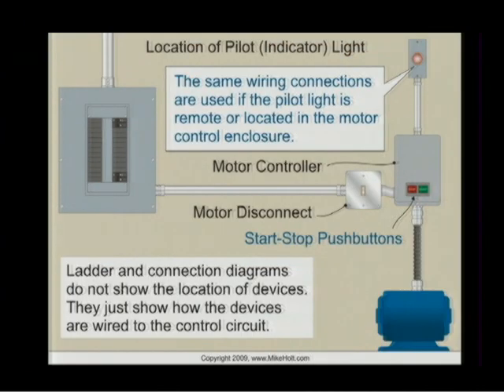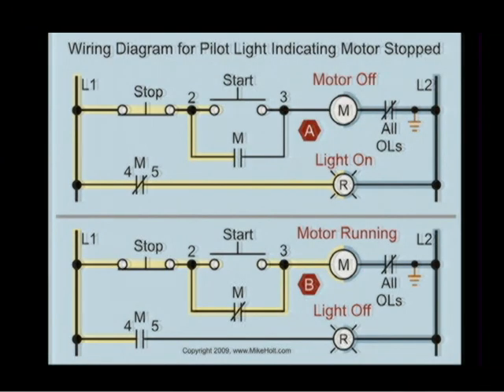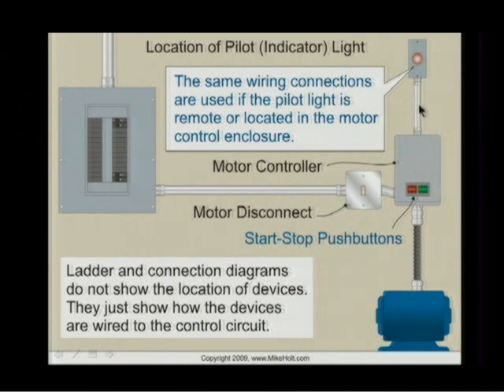All right. And where do you locate the pilot light? Of course. Oh, let's see the wiring. The wiring of the pilot light is going to be coming from the contactor, going back to the contactor in parallel to the M coil. So right here, I'd run how many wires up here? Just 2 wires. And it doesn't matter if this is a quarter mile away. It's just 2 wires to turn on that light. It gets in parallel with the coil. So the key here is to get in parallel with the coil.